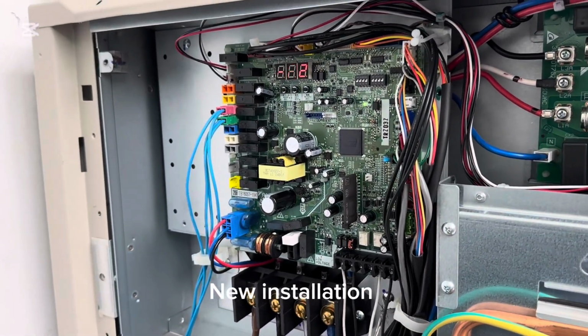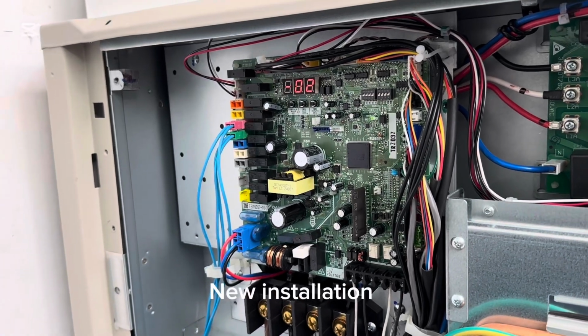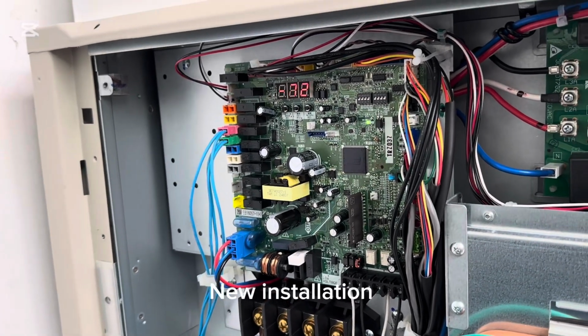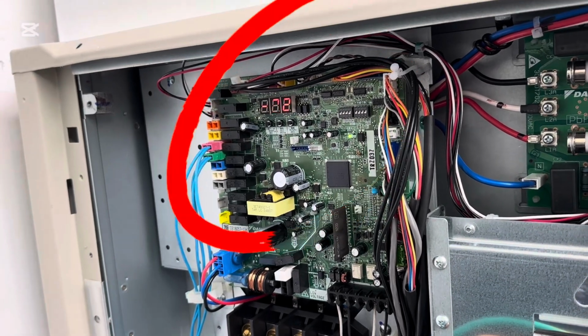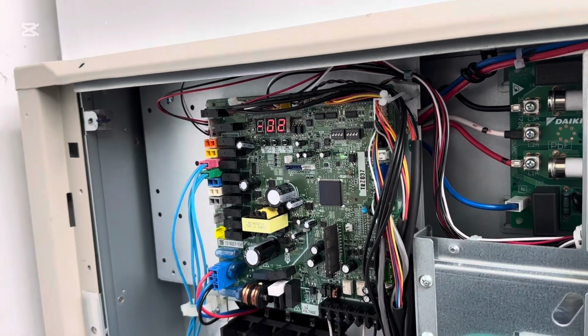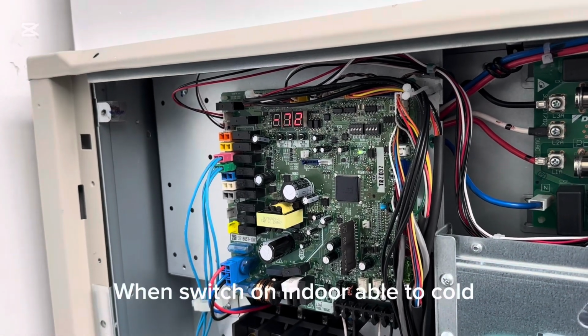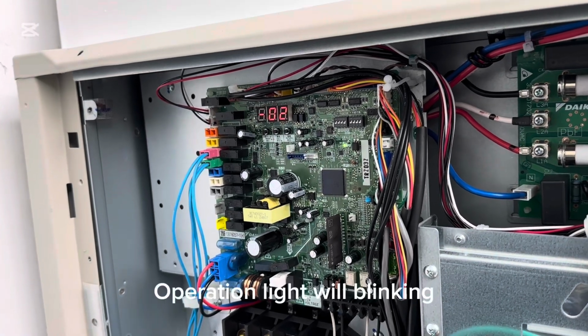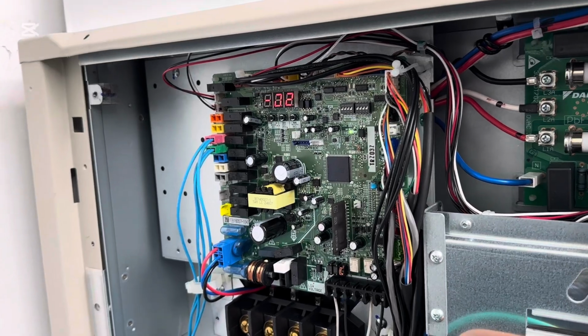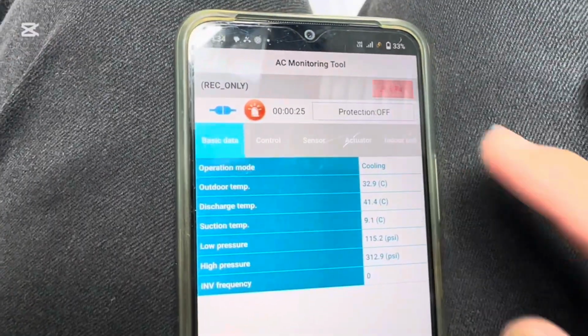This is a new installation, Daikin VRV4. We found one of the indoor units, the LEV, unable to close, and it becomes the error F4-02. But when you switch the indoor on, it is able to cool and is okay, but the operation light will be blinking. The error is F4-02.